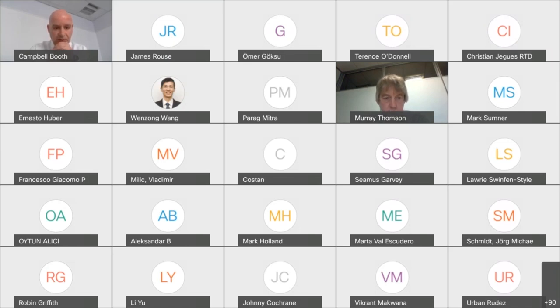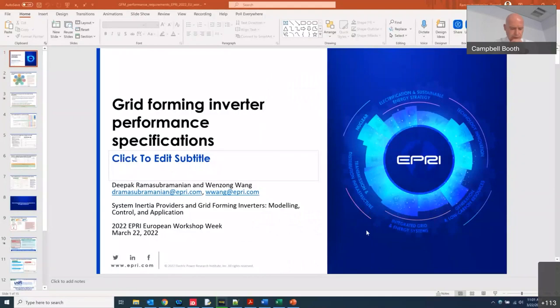Thank you. Thanks, Campbell. Can you hear me? Yep. Okay. So the way we have structured this is, from Wenzong and my side, we'll provide a little bit of perspective regarding grid forming inverter specifications that we've been working on. And Thibaut will provide a perspective from some synchronization capability work that they have been doing at RTE. And the goal here is to try to converge on some kind of scenario wherein, without really knowing what the control type inside the grid forming inverter is, we can have a performance derived.